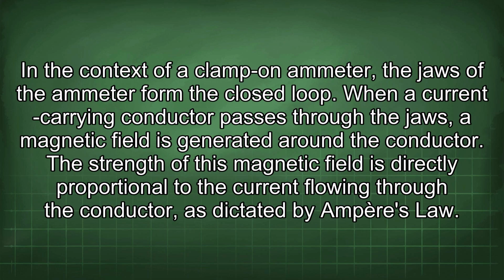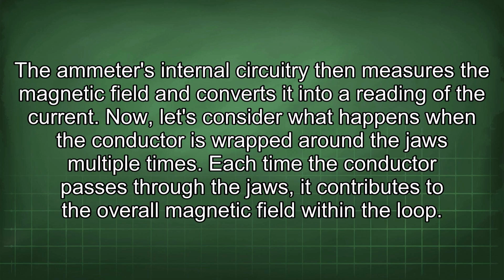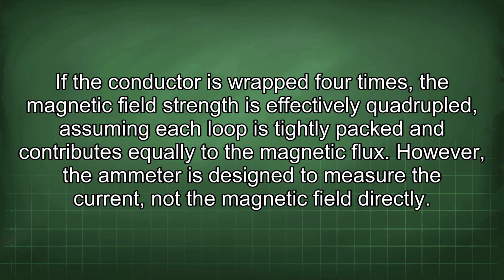In the context of a clamp-on ammeter, the jaws of the ammeter form the closed loop. When a current-carrying conductor passes through the jaws, a magnetic field is generated around the conductor. The strength of this magnetic field is directly proportional to the current flowing through the conductor, as dictated by Ampere's law. The ammeter's internal circuitry then measures the magnetic field and converts it into a reading of the current. Now, let's consider what happens when the conductor is wrapped around the jaws multiple times. Each time the conductor passes through the jaws, it contributes to the overall magnetic field within the loop. If the conductor is wrapped 4 times, the magnetic field strength is effectively quadrupled, assuming each loop is tightly packed and contributes equally to the magnetic flux.